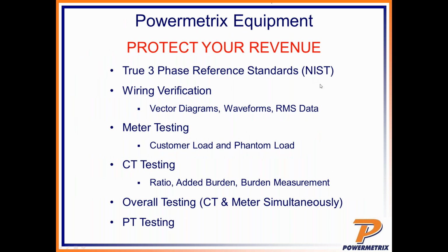We'll get into the meat of it. Just want to do a quick review of what Powermetrix does and what our equipment does. So we're here to protect your revenue stream, right? All the products that we use to test CTs have true three-phase reference standards. Those are traceable to NIST. And our products try to find all the lost revenue on your site. So we look at wiring verifications, which is what do our vector diagrams look like? What do our waveforms look like? What does our RMS data look like? We can test the meters for you under customer load and phantom load.